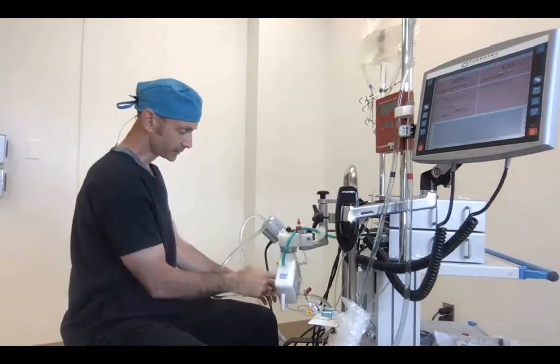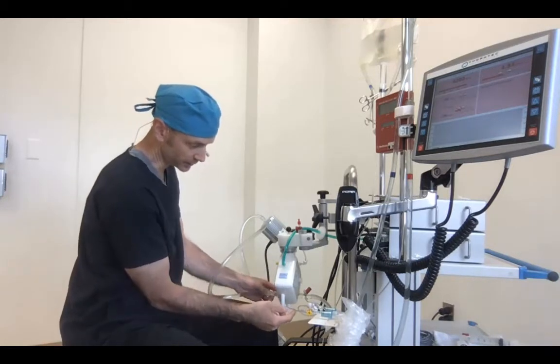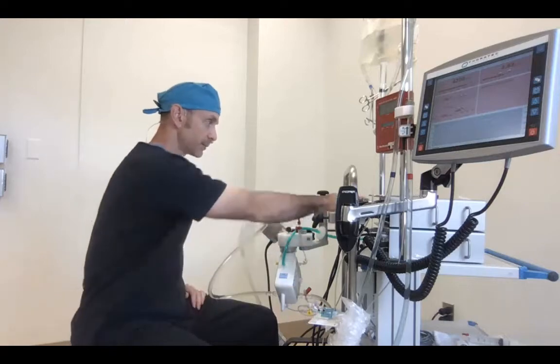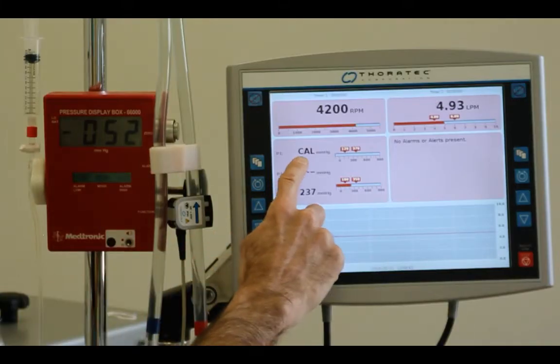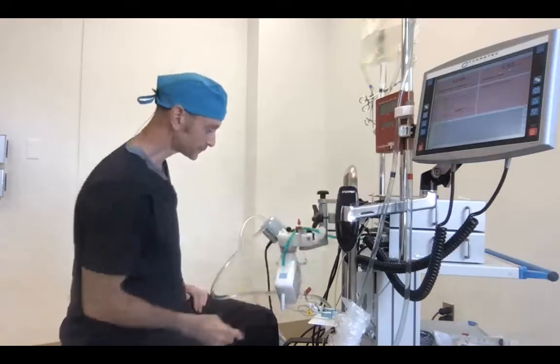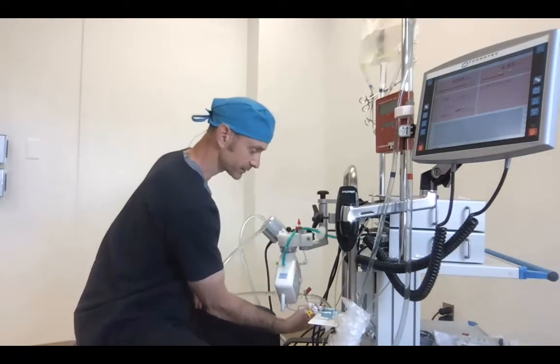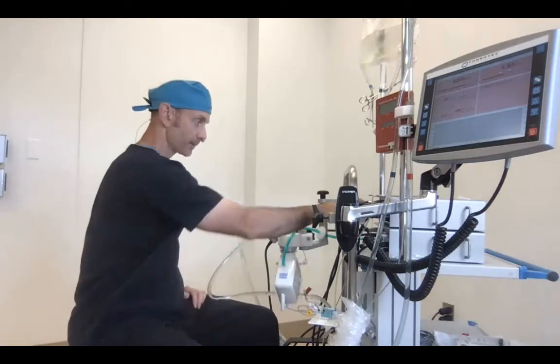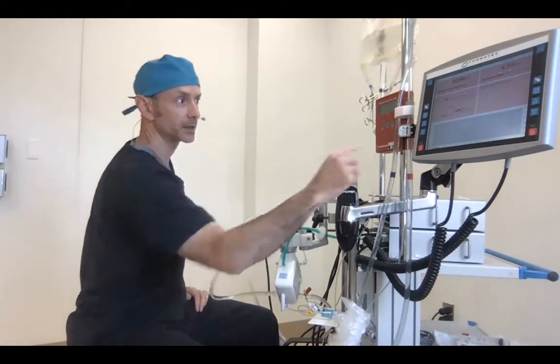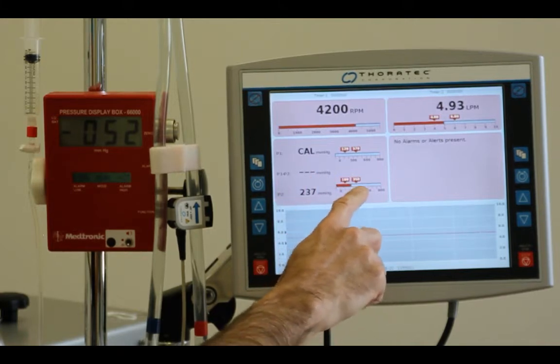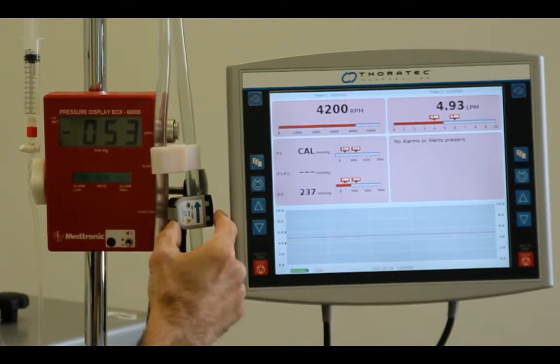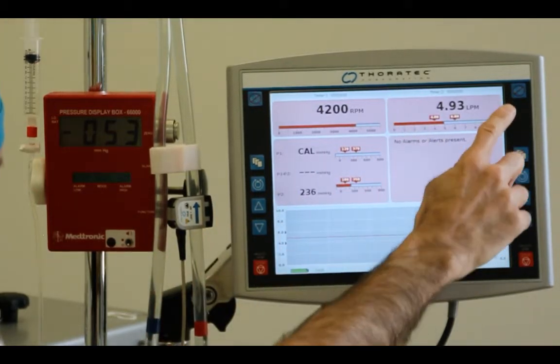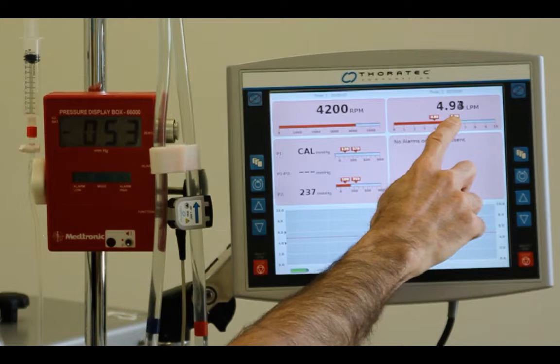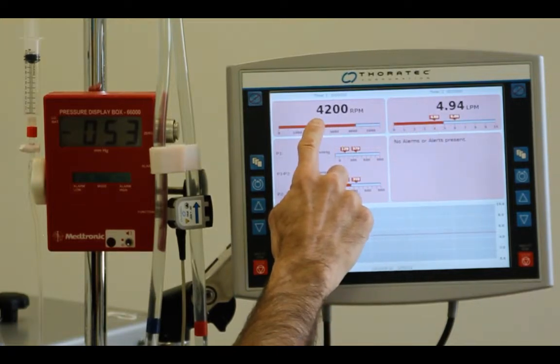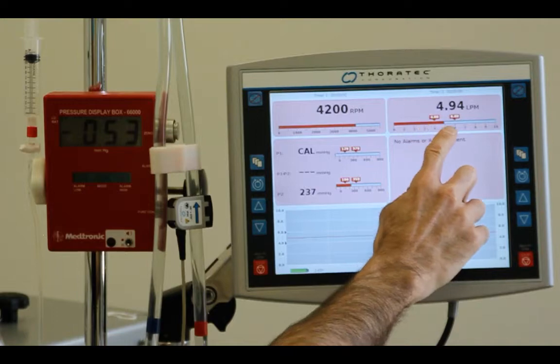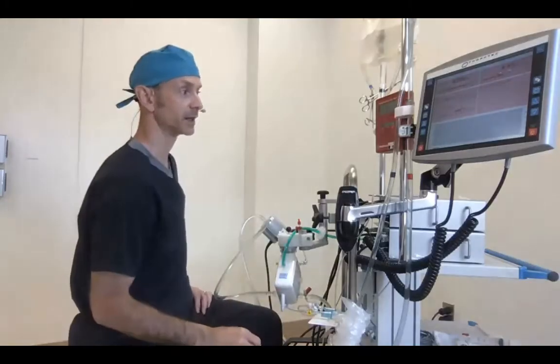The pre-membrane side of the oxygenator has a line connected to P1 on the back of the Centrimag, and that's displayed over here. We'll calibrate that in a second. The post-membrane side of the Quadrox is connected to P2, and that is being displayed here. I've already calibrated that and set my limits. The flow is displayed on the screen at 4.93 liters a minute at an RPM of 4,200, and I've set some brackets of 4 liters and 6 liters around my flow of approximately 5.